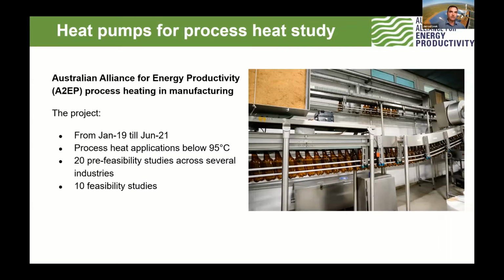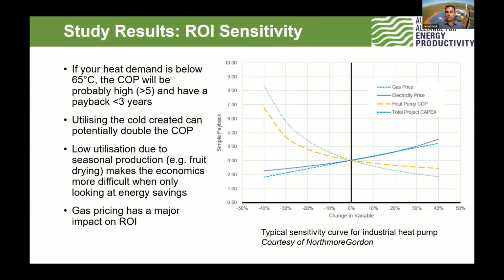We've seen very good results from that, and we're starting to understand the sensitivity of heat pump applications in terms of ROI. We can see clearly that anything below 65 degree temperature demand will get a coefficient of performance above 5, and a payback of less than 3 years just on energy savings alone.